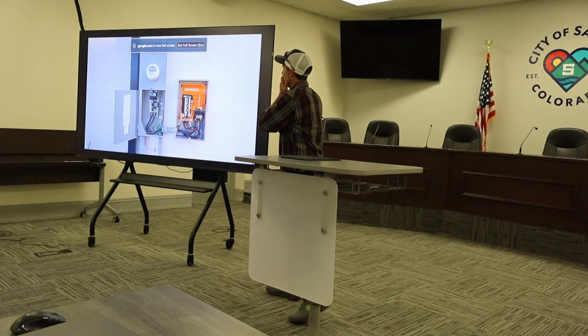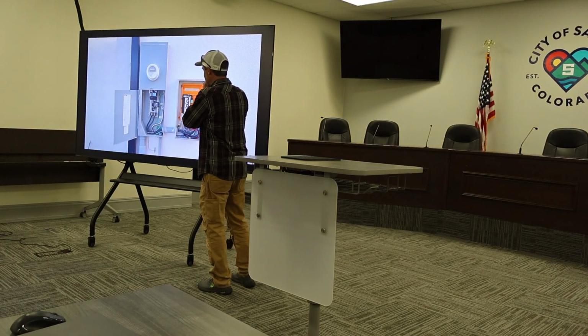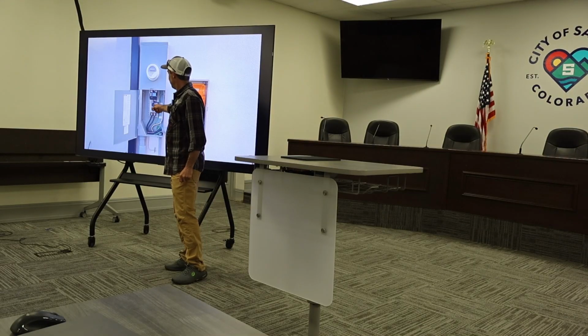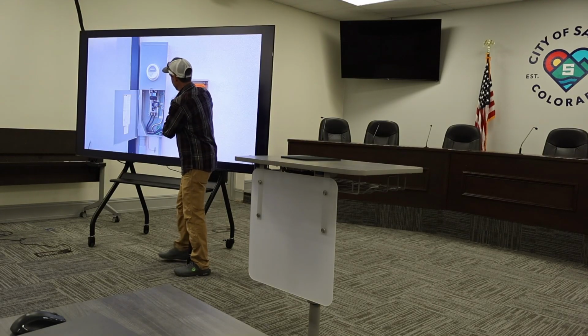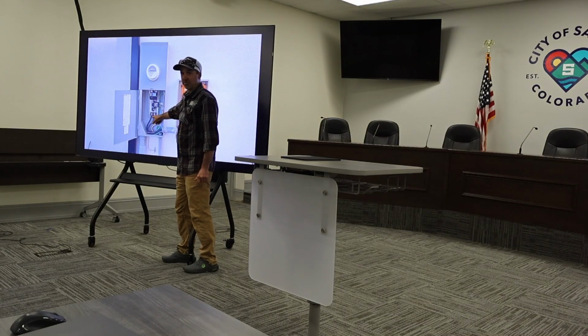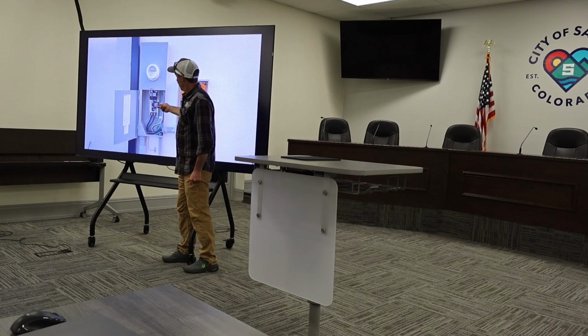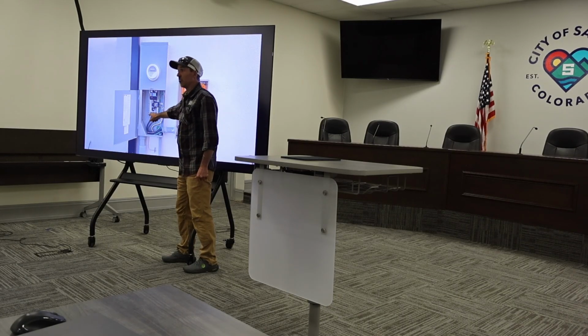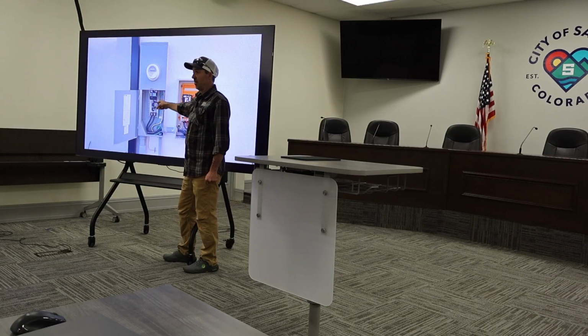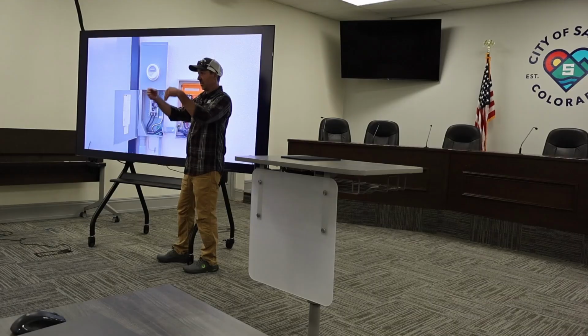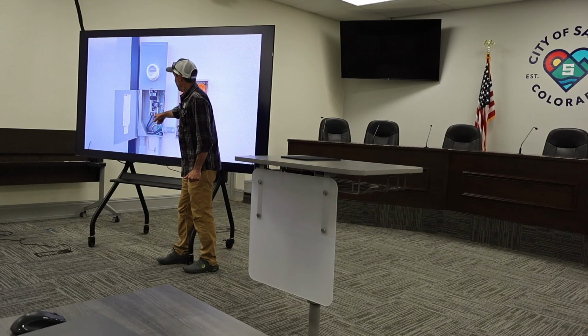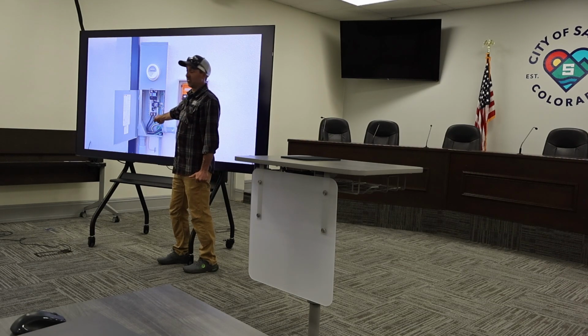Let's say this didn't have a transfer switch and we're just connecting solar. The reason we can't just land our solar breaker here, and why we have to use a meter collar, is these conductors. If this is just going into a panel, these conductors are rated for 200 amps because that's what the breaker is. If we put solar into this, we're creating a parallel connection, so these conductors could see 200 amps from here but also maybe 40 or 60 from our solar, and they're not rated for that. This breaker doesn't see our line voltage or current as a load because it's not pushing power to it, it's just our feed connecting on and paralleling. So even though there are breaker spots here, we'd have to do a meter collar to meet this.